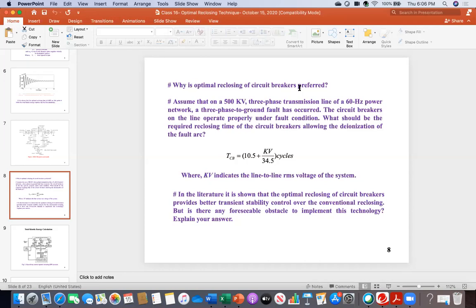If you just wait until the arc extinguish time and immediately reclose, the performance is much better. But the conventional system, because it is predetermined and fixed, waits 1 second, I have seen 1.4 seconds, a longer waiting time. As early as you can reclose the breaker, that is better for the system, for the connected people. If it is a temporary fault and the arc has been extinguished, the fault has been cleared, then why not reclose it early? Why do we have to wait? That is the limitation or drawback of the conventional system.